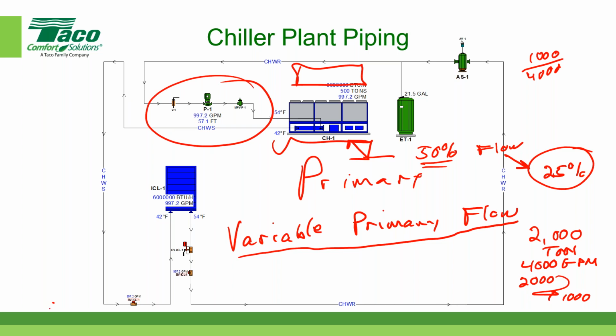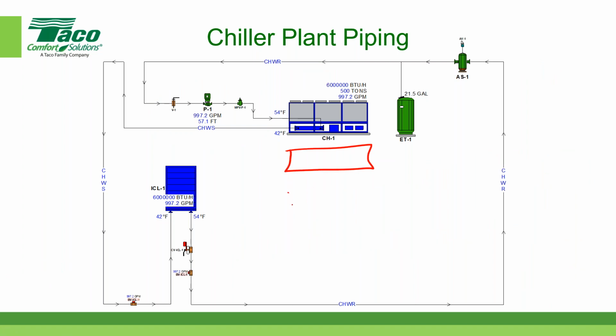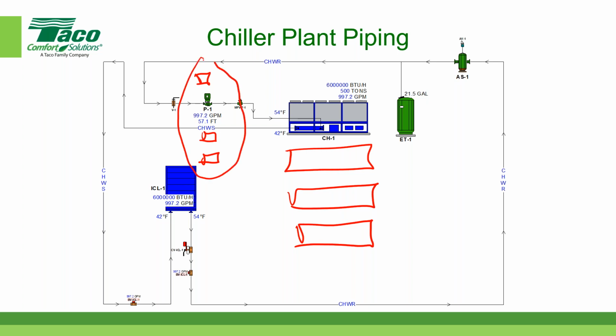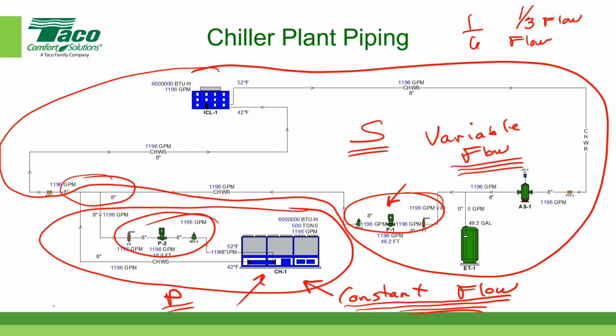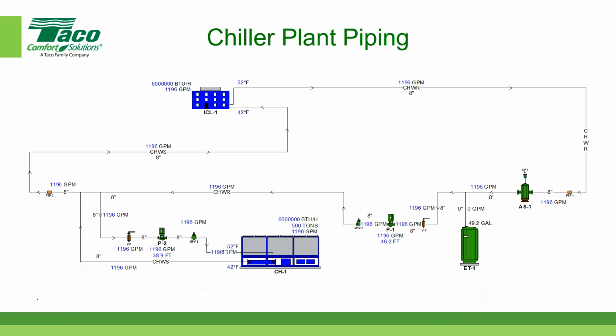Well, let me erase some things. We're getting a little bit crowded here. So there's one chiller, 2 chillers, 3. I could use as many chillers as I wanted in any of these systems. And then I'd have multiple pumps. There's 1 pump, there's 2 pumps, 3 pumps. But I'd only have, for a variable primary flow, one set of pumps for the chilled water side, as opposed to back here. Whoops, I got too many lines drawn here. Let's see if I can erase that. In a primary secondary, if I had multiple chillers, I would have multiple pumps on the primary side and multiple pumps on the secondary side.